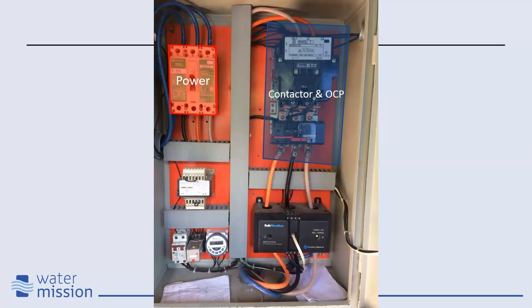A couple other items that we should point out here is going to be this right here. This is another transformer. So this system is a 480 volt system, but this timer doesn't want 480 volts, it wants 110 volts. So this is stepping down the power to what your control system wants.